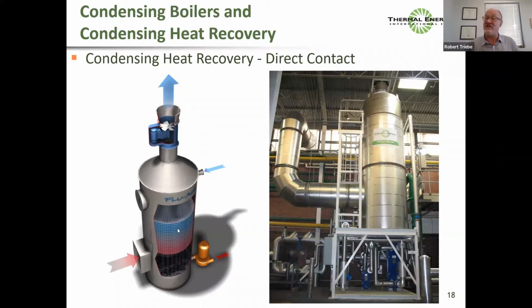Here you can kind of see there's sometimes packing. Most frequently, some kind of packing can be random, can be structured, can even be an open tower. But this is a direct contact condensing economizer. So you can see these 4 technologies are really just 2 technologies, and all they are is heat exchangers. And the only question is, do I have a burner in it or not? So, the 4 technologies really reduce quite simply to direct or indirect contact heat exchangers with or without a burner.